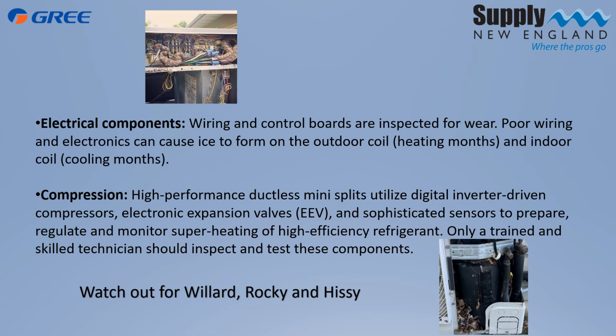We're going to check those EEVs. That's actually where I see a lot of the issues are. So I like to take my EEV coils off, get in there with my wire brush, clean them if they're dirty, wipe them off, and then put them back into place.